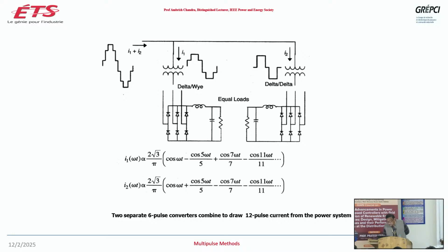So if you take the sum of these, this will cancel out, this will cancel out, and the 11th harmonic is added. Similarly, the 13th harmonic as well. So it means that it is not helping with the 11th and 13th harmonics, but again the 17th and 19th harmonics are cancelling.